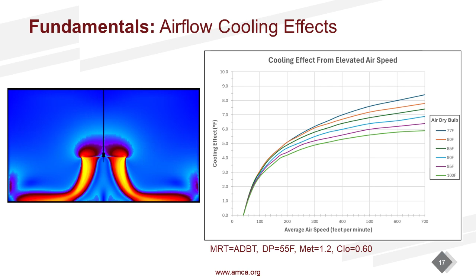Where we generally play in commercial or industrial spaces, we're typically in that 200 to 300 feet per minute range from an HVLS fan or a directional fan. Even between 77 degrees and 100 degrees, we're only looking at about a 1 degree difference in total cooling effect to the occupant. We'll talk about how effective air movement can be even at the further extremes, into the 105, 106, 107 degree Fahrenheit conditions we see.